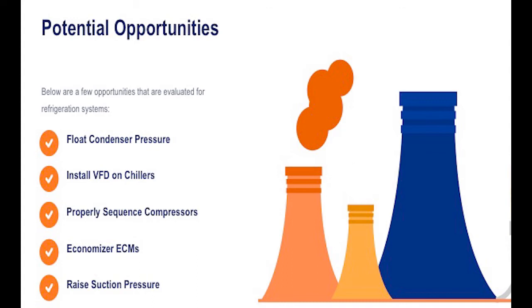For evaporator ECMs, we'll look at the evaporators in the system to see what opportunities exist, whether it be cycling the fans depending on if they're calling for cooling or not. We'll look at defrost controls on those units as well. So it's a pretty comprehensive energy survey on the refrigeration system.